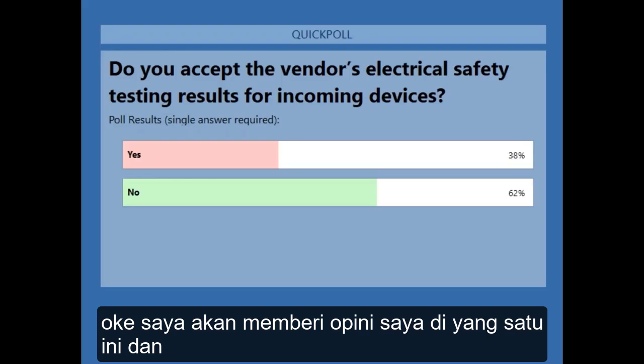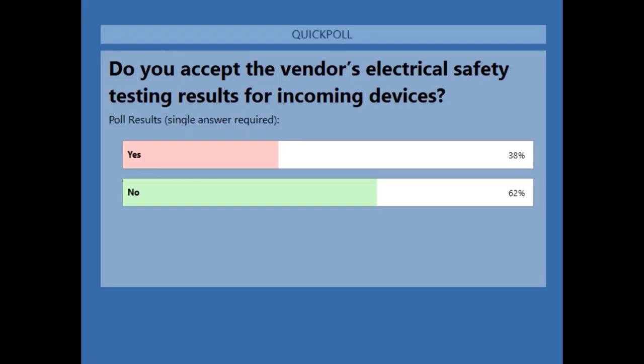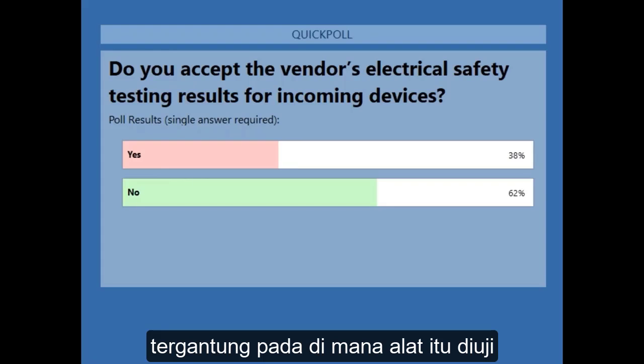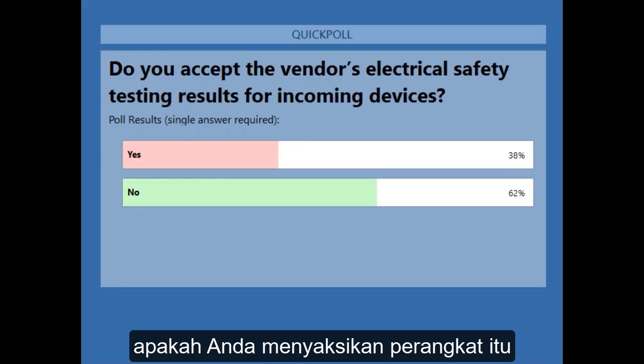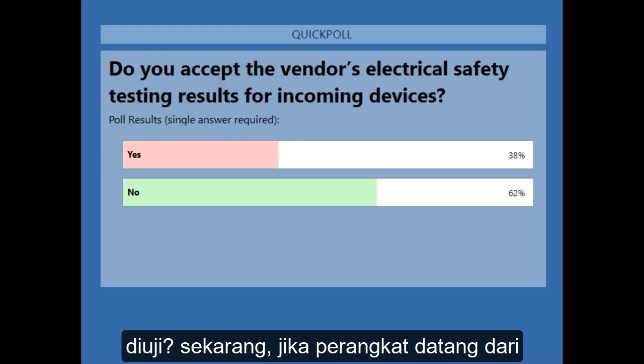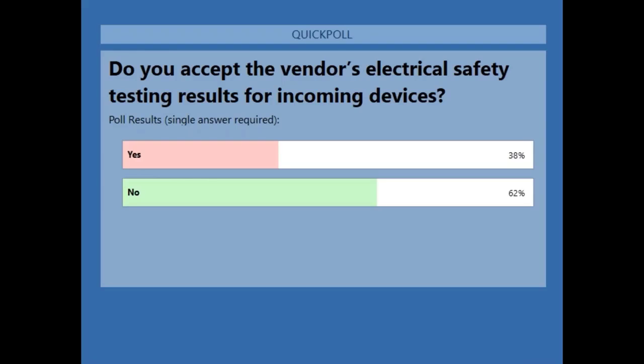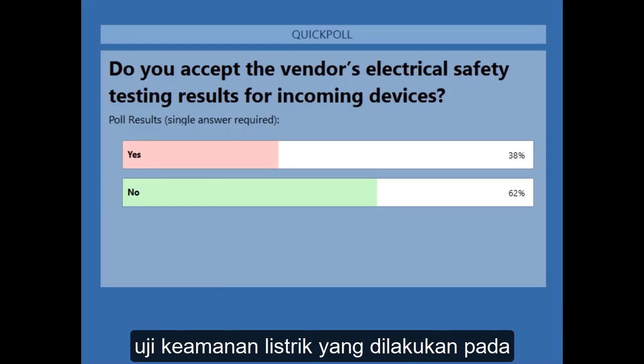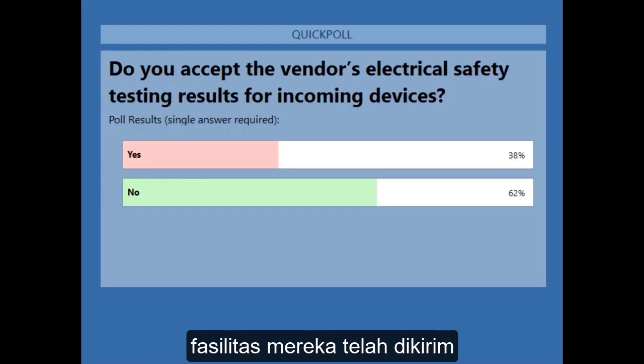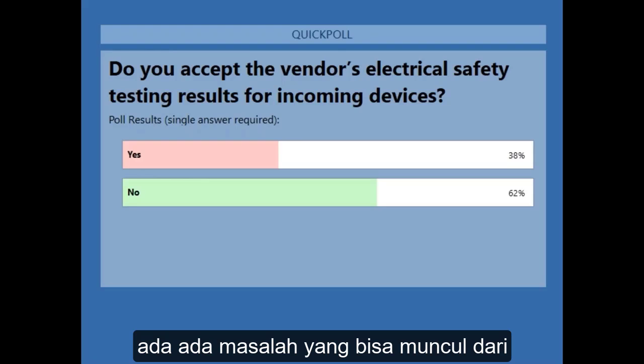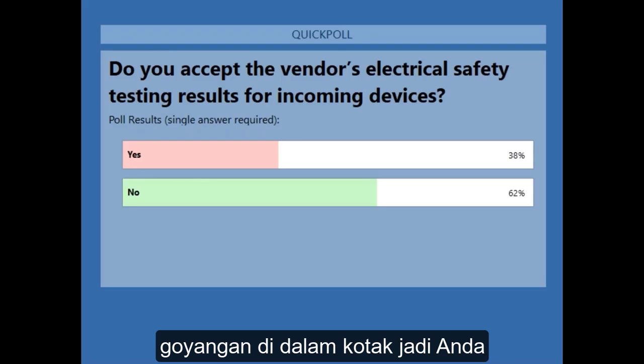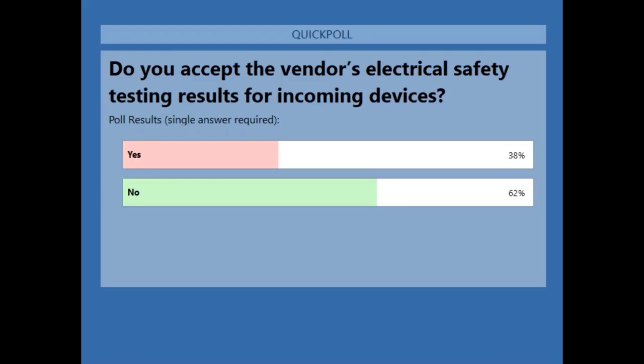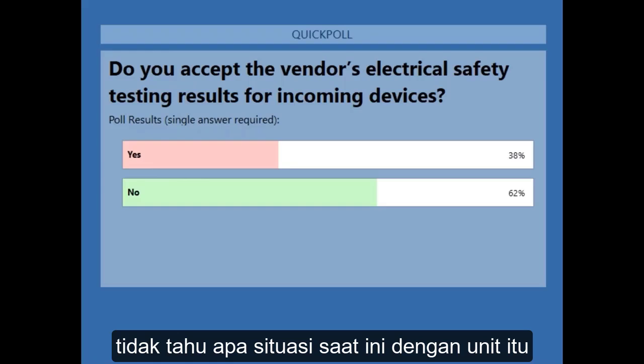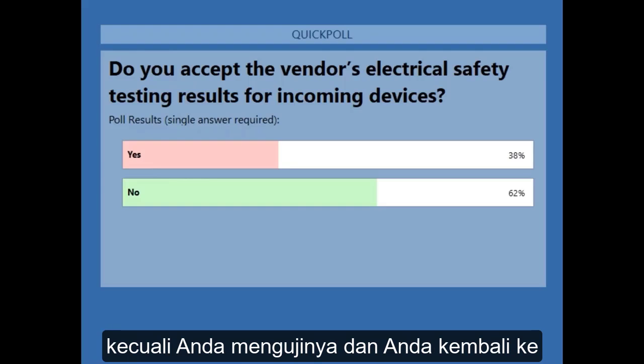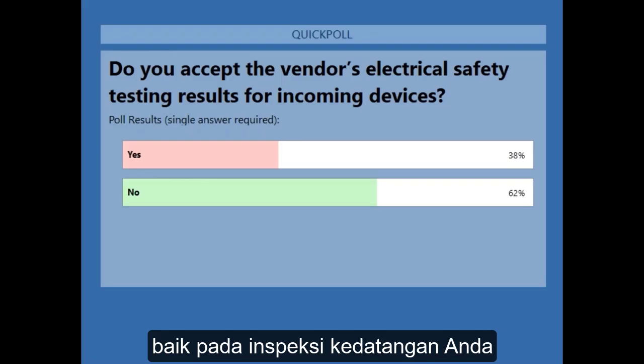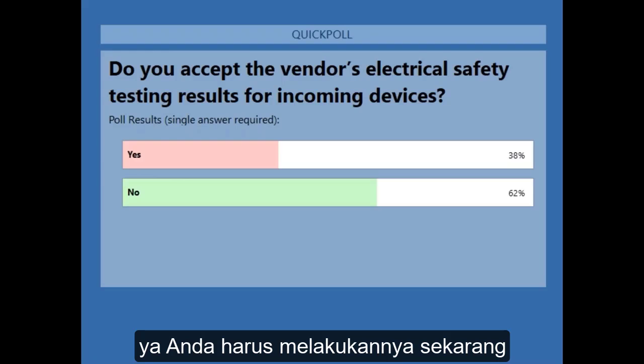Okay, I'm going to weigh in on this one, and you can go either way - it really depends on where the device is being tested. Are you witnessing that device being tested? Now, if a device comes in from a manufacturer with a service report showing the electrical safety test, that was done back at their facility. It has been shipped, and issues could come up from it rattling around in a box. So you do not know the current situation with that unit unless you test it.